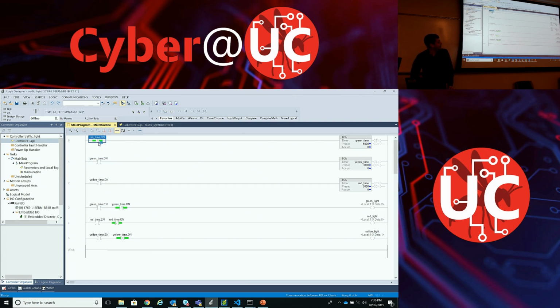The other one is this symbol up here. It looks the same as the last one, but it's got a slash through the middle. This is the opposite, called examine if open, versus examine if closed, which is essentially an if-false. So if no power is going into the thing you're looking at, it will say, okay, close the circuit.